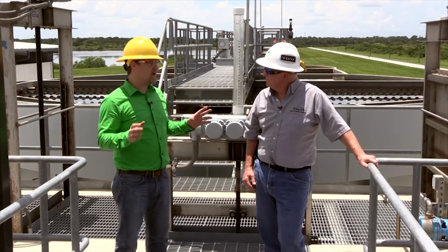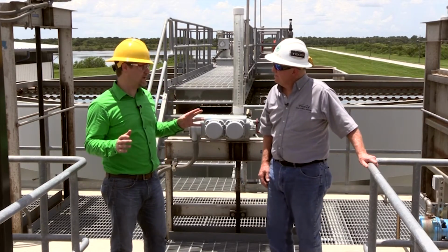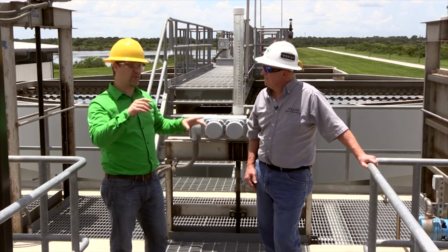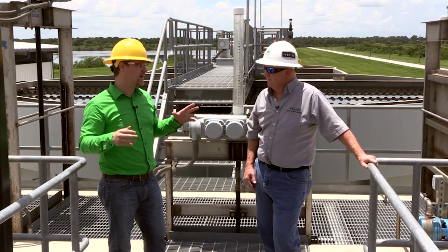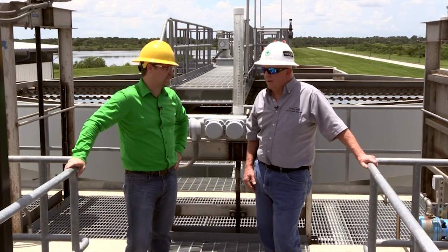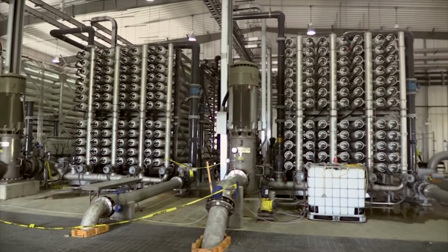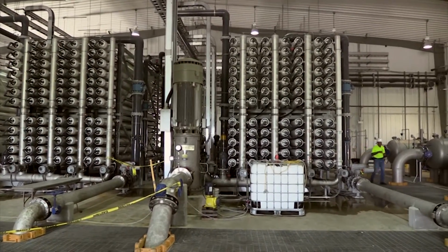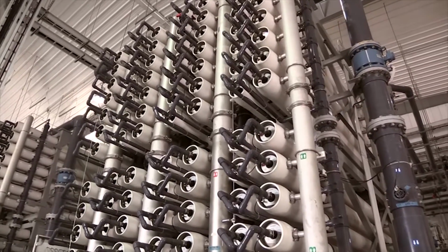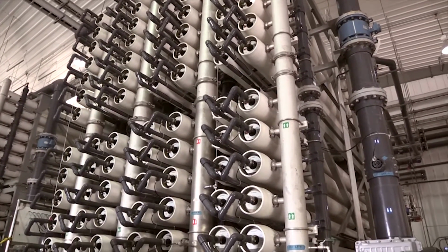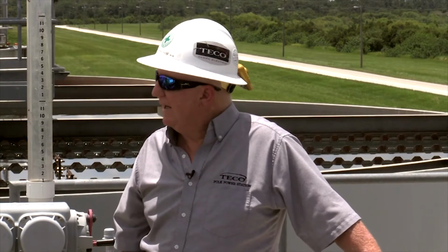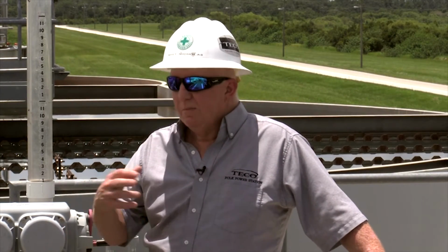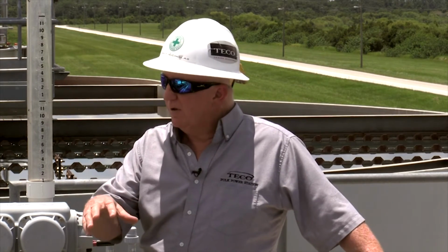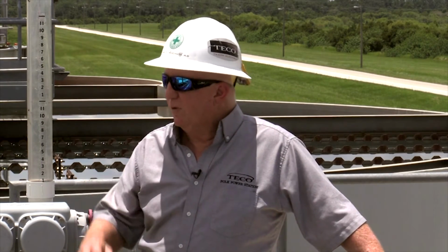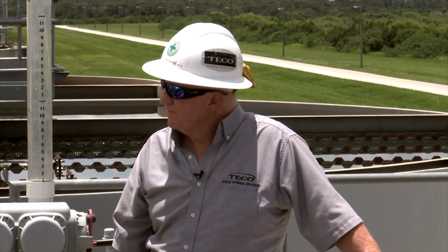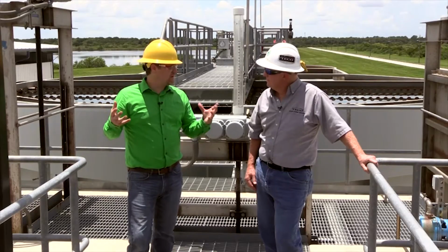Mike said the reverse osmosis units here are pretty big, not like the ones at the other plant we're going to look at later. These can handle 2,000 gallons per minute. Each skid is capable of processing about 2.8 million gallons per day. We currently have 2 of those skids, giving us a capacity of about 5.6 million gallons per day. But we're currently expanding to a 3rd RO system to enable us to go to a full 8.5 million gallons.